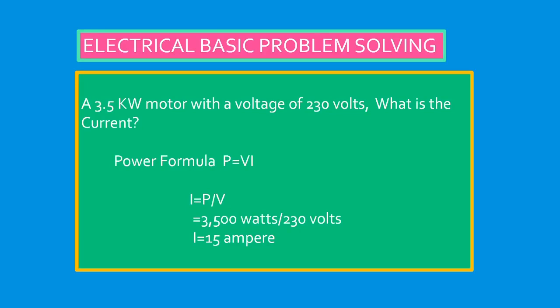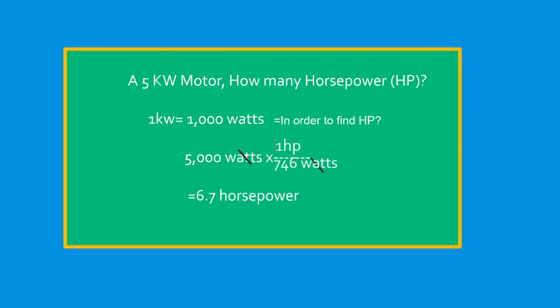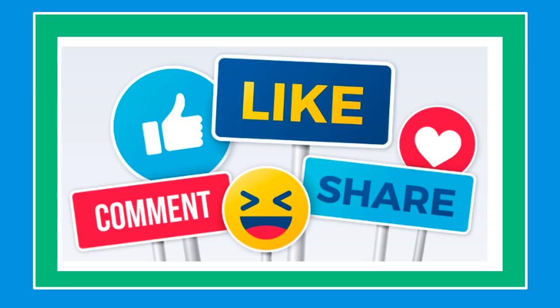This is the application of the formula we discussed previously. Example: A 3.5 kilowatt motor with a voltage of 230 volts, what is the current? Power formula: P = VI, so I = P/V. 3,500 watts (because we know 1 kilowatt is 1,000 watts) divided by 230 volts, so the answer is 15 amperes. Next question: A 5 kilowatt motor, how many horsepower? We know that 1 kilowatt equals 1,000 watts. In order to find horsepower: 5,000 divided by 746, the result is 6.7 horsepower. Thank you for watching and see you on the next video. If you like this video, please like, share, and subscribe. Have a good one.